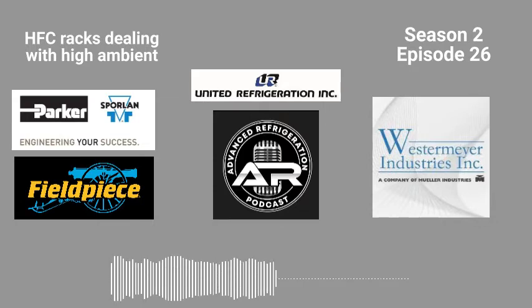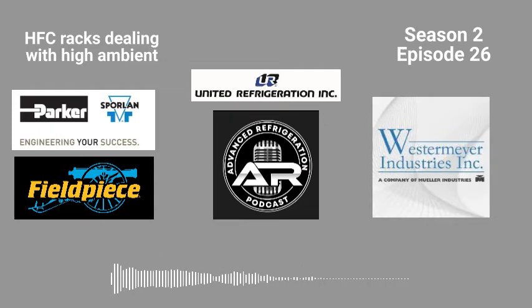Yeah, I mean that's one thing. Now, guys, just for example, we're talking about these fans and everything, going up to a condenser, and it may look clean on the bottom. One is impacted. So an impacted condenser, two things, telltale sign: you're going to have higher amp draw on your motors, and you're going to have air coming out the side. If there's air coming out the side of the fan blades, whether it be a horizontal condenser or a single unit condenser, if it's not coming straight out and it's coming out the sides, it's an impacted condenser. It's dirty. The same thing will happen if it's plugged with cottonwood, you're going to have air coming out the sides, not the top. So that right there tells you it's impacted.